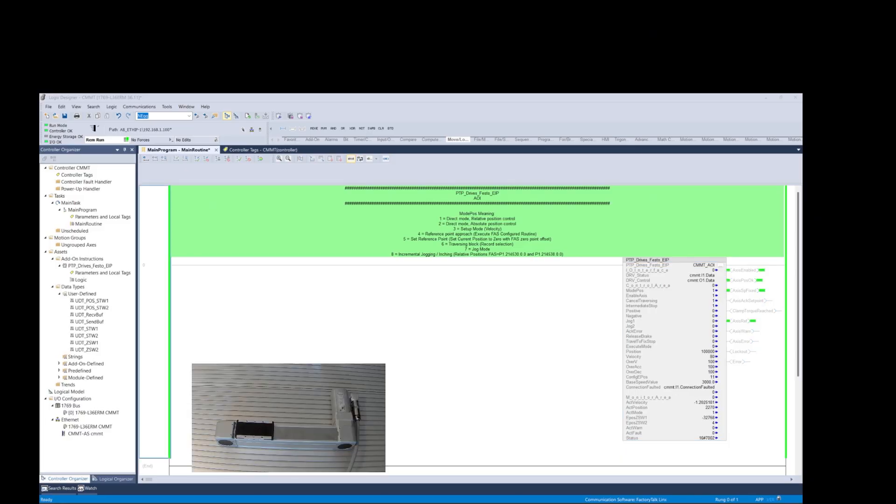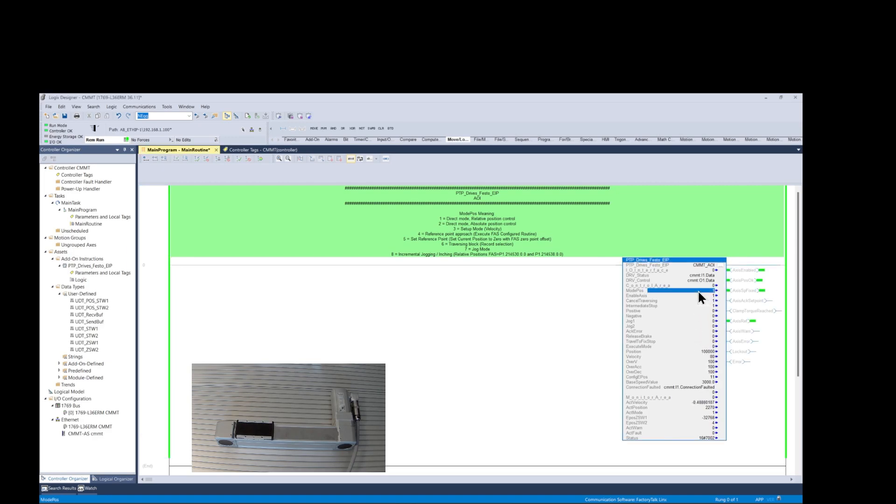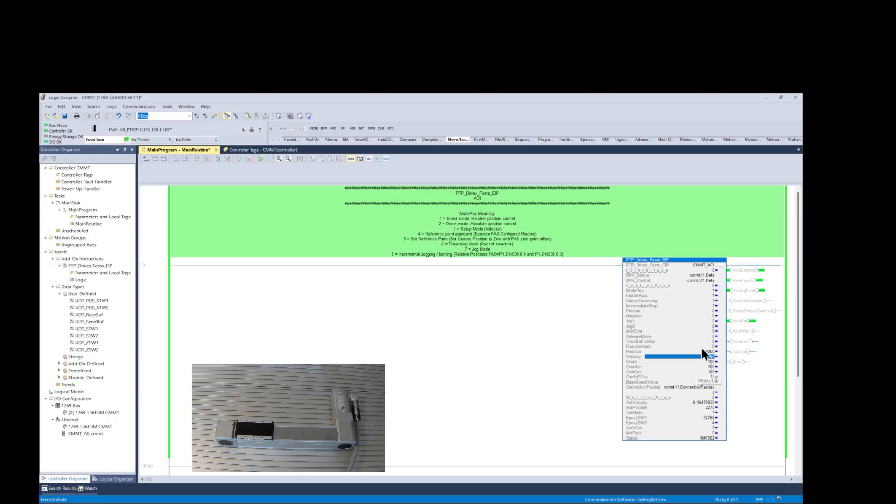Now let's run some incremental moves. We begin by changing the ModePos value to 1, then position value to 100,000, which equals 100 millimeters, a velocity value of 80, which equals 0.08 meters per second. And then we set the execute mode value to 1 to begin the move. We always toggle the execute mode after each move.